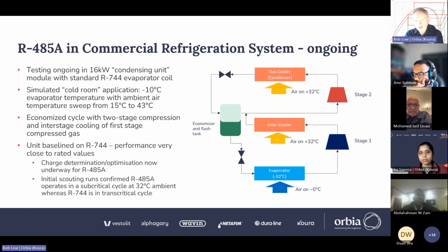And it rejects heat out through a gas cooler, but it's got a more sophisticated compressor. It's a two-stage rotary scroll compressor. The gas from the first stage of compression is cooled with ambient air before it's injected into the second stage. The cycle is also economized, so the hot, high-pressure gas is flashed down to an intermediate pressure in a flash tank, and then the flash vapor is taken into the second stage of compression along with the cooled gas from the first stage of compression. Then finally, the liquid from the flash tank is metered into the evaporator. So you get the benefits of the economized cycle effect here, with better heat transfer in the evaporator with less flash gas going through the evaporator, and reduced compression work overall.